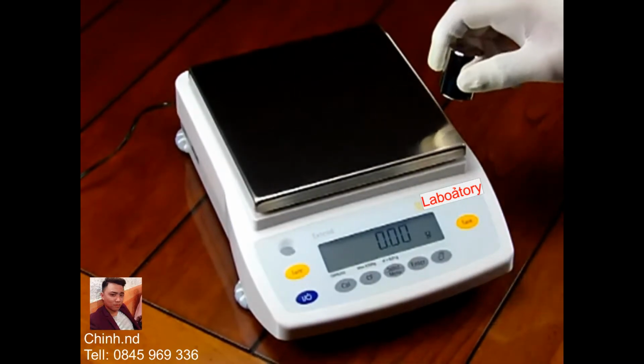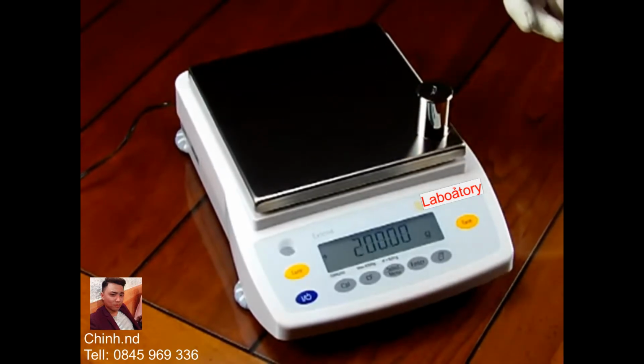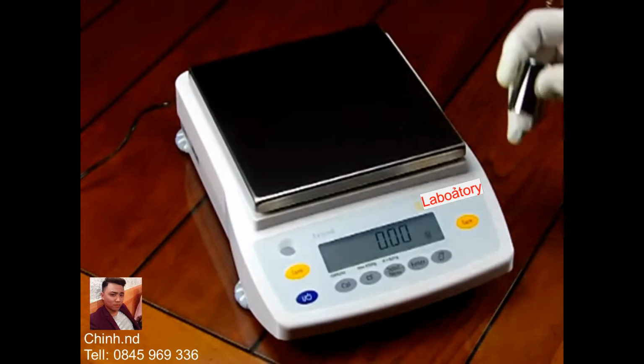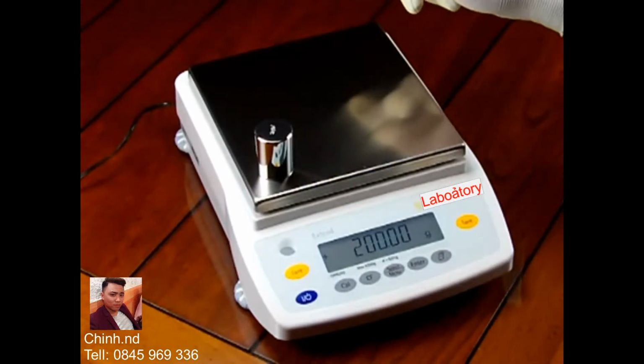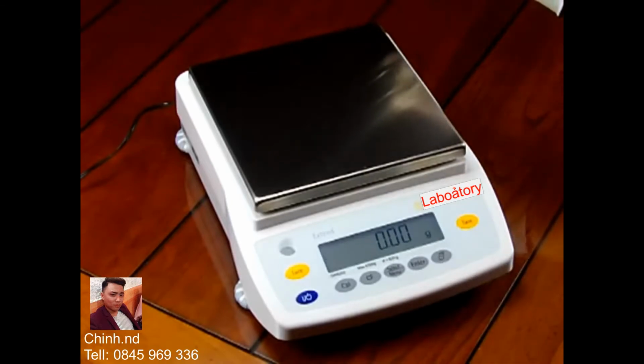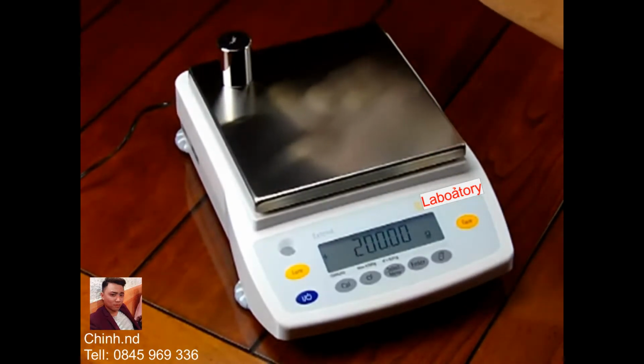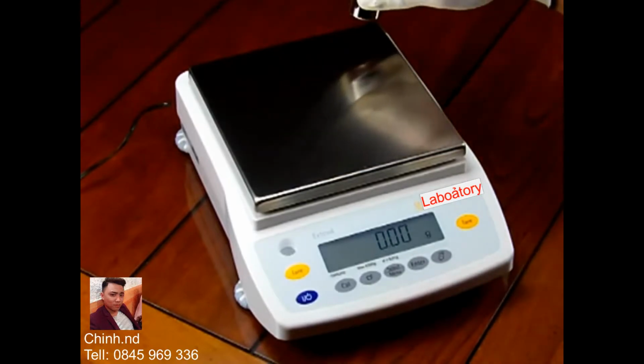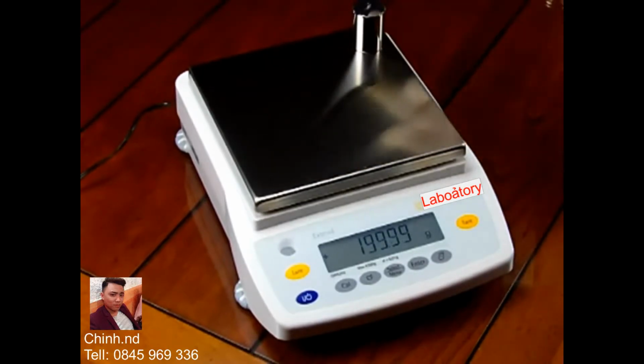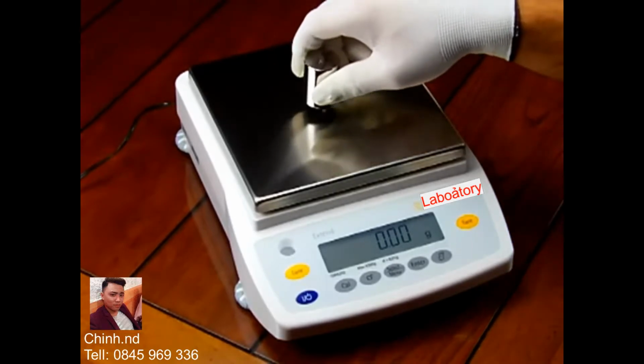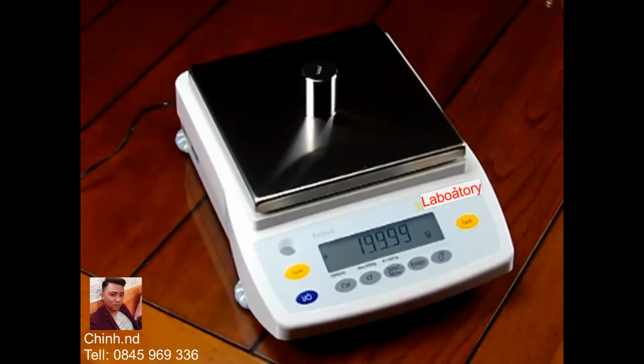And so we have a 200 gram calibration mass, and we're just going to try to show you how fast the balance responds. So we're just putting the 200 gram weight in each corner, and you can see this balance is lightning fast. And you'll see each time the balance returns to 0. Now, the readability again is 0.01 gram. So we're going to leave this test mass on the balance just to show you there's minimal drift. Sartorius is using a monolithic cell, and it offers spectacular performance.